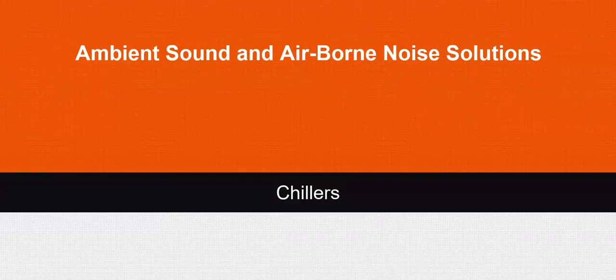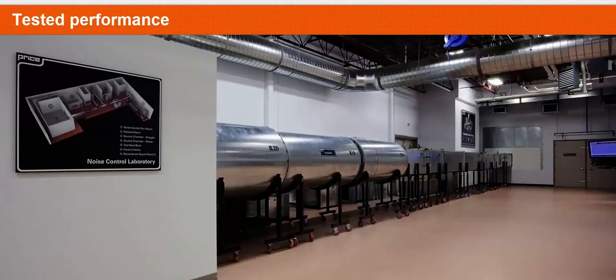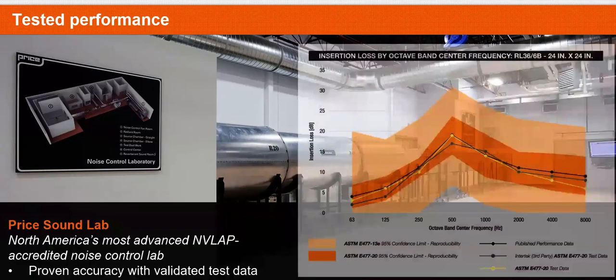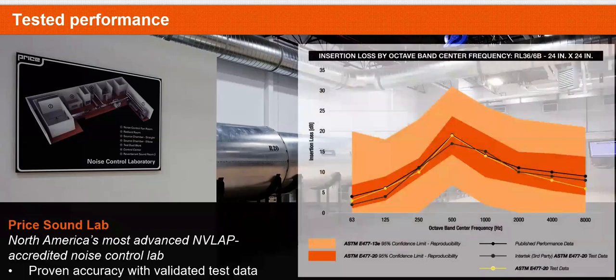Moving on, we're going to talk about chillers now, some of the solutions that we use for that. What we use is noise control products derived with tested data that's accurate. So that is the main message of this slide. Whenever you're having to provide openings on an enclosure, in this case on a chiller for the exhaust at the top or on the compressor side at the bottom, then you need to maintain the transmission loss of that enclosure. And how do you maintain that?